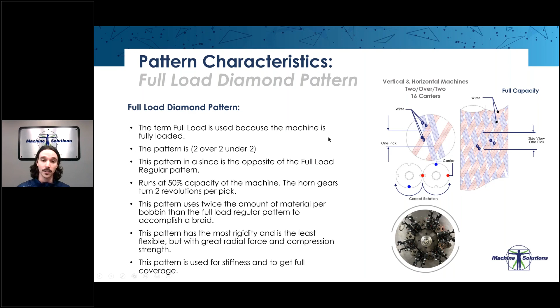It's the opposite of the full load regular in that sense, also for flexibility. It's not known for flexibility, it's known for its stiffness and rigidity. It does have good radial force and compression strength due to those variables, but it's typically used in things like endoscopy. I see it a lot in endoscopy. So yes, the full load diamond pattern is twice as slow and uses twice the amount of material. From a throughput standpoint and a cost standpoint, it's not the most ideal pattern, but it can be used for good coverage and if you need that stiffness and rigidity.